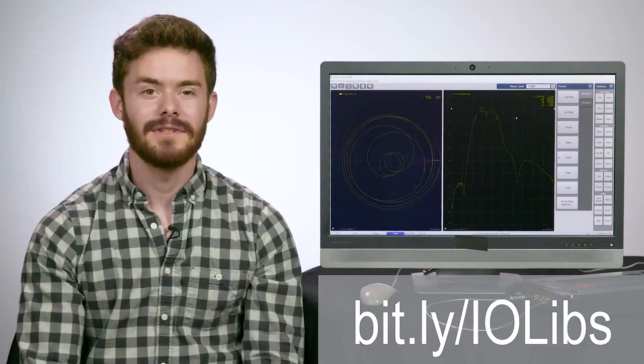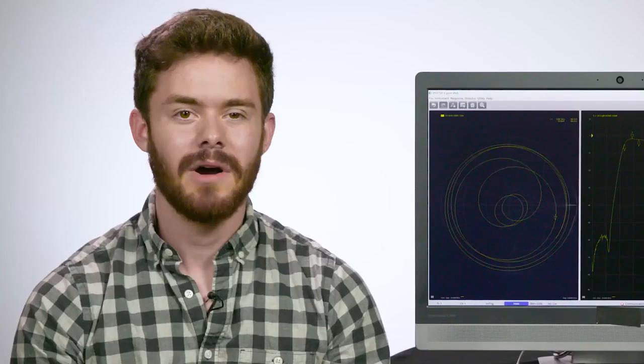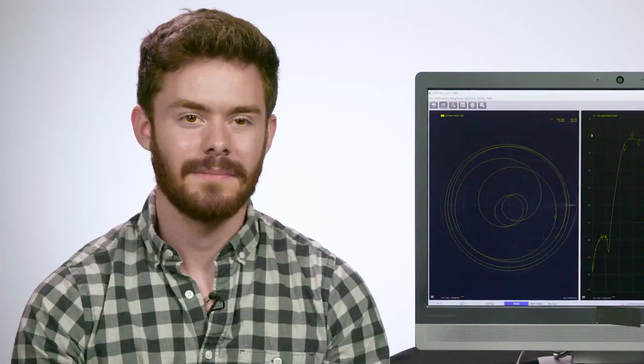First things first, before we actually dive into how to use this new type of instrument, we have to get the software downloaded and ready to use on our PC so that we can actually control this box. The first thing you have to do is download the Keysight IO Libraries at the link on the screen. This is what will allow you to connect instruments to your PC and manage those connections.